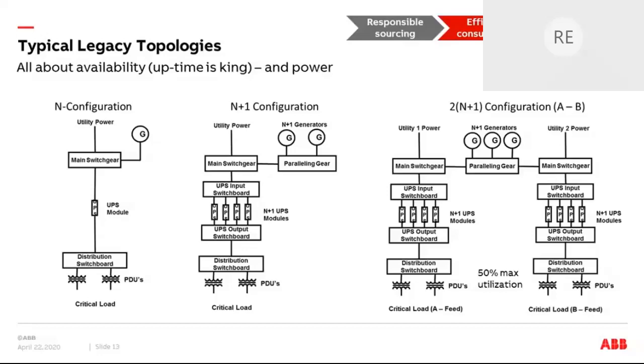With that in mind, let's take a look at the topology, the infrastructure around it. ABB, of course, is an electrification manufacturer, and a lot of what I look at every day has to do with topology. On the far left, we see the original configuration, which just allowed you to run the critical load. You had a UPS to filter and keep power quality up, and on the main switchgear we had the choice between running a genset or running utility power—an effective way to run the data center.